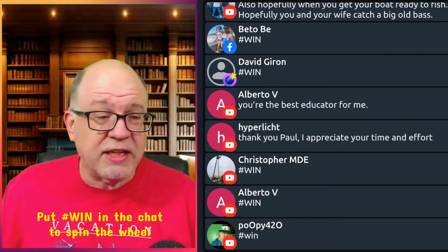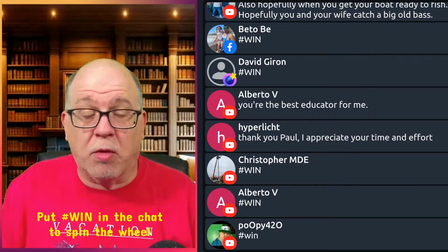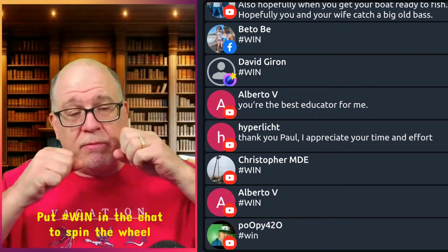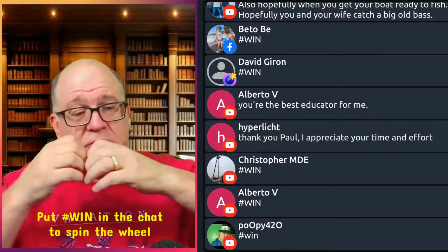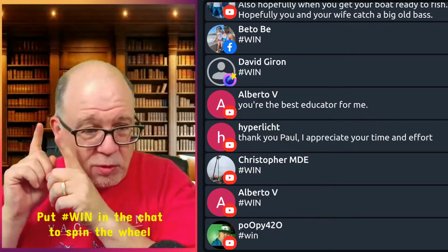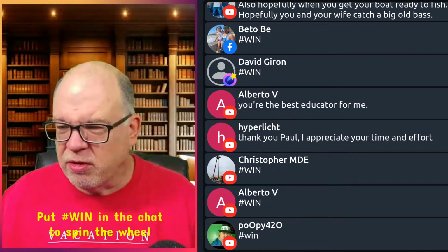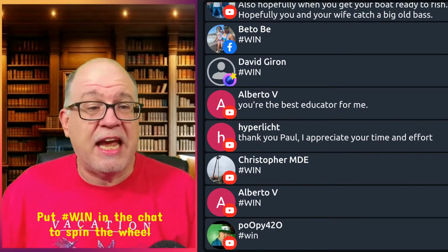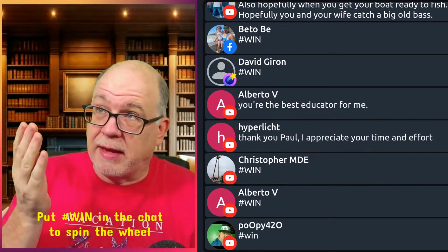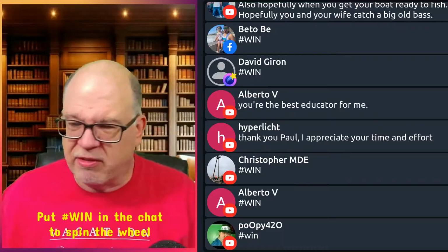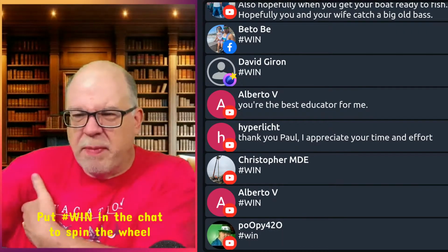Grouping of the conductors. You saw that if they come in a raceway and you've got multiple circuit conductors and multiple shared neutrals, you need to identify them and put a tie wrap or some type of identification. Some people just use white tape or whatever to segregate them out so that we know exactly which neutral goes with those hot conductors that are used with that shared neutral. The exception to that, if it's a cable, then it's obvious. There's no need to do that because obviously I can look at a cable and see that that white goes with those black and reds or whatnot. So that's not a problem. Let's see. What about...